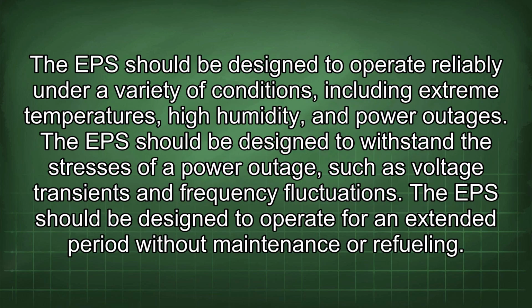The EPS should be designed to operate reliably under a variety of conditions, including extreme temperatures, high humidity, and power outages. The EPS should be designed to withstand the stresses of a power outage, such as voltage transients and frequency fluctuations. The EPS should be designed to operate for an extended period without maintenance or refueling.